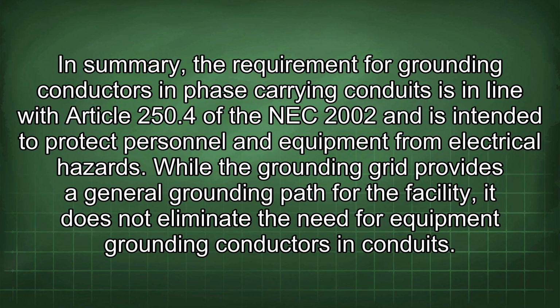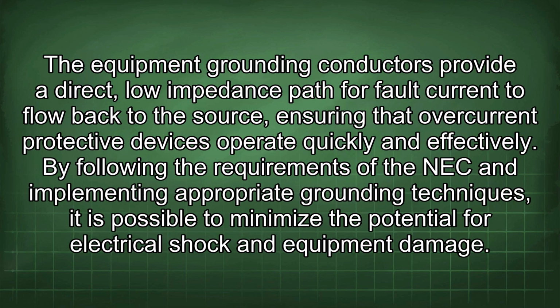In summary, the requirement for grounding conductors in phase carrying conduits is in line with Article 250.4 of the NEC 2002 and is intended to protect personnel and equipment from electrical hazards. While the grounding grid provides a general grounding path for the facility, it does not eliminate the need for equipment grounding conductors in conduits. The equipment grounding conductors provide a direct, low-impedance path for fault current to flow back to the source, ensuring that overcurrent protective devices operate quickly and effectively. By following the requirements of the NEC and implementing appropriate grounding techniques, it is possible to minimize the potential for electrical shock and equipment damage.